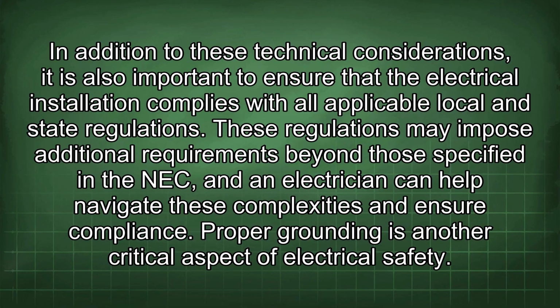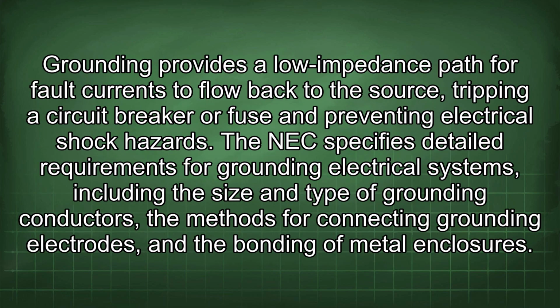Proper grounding is another critical aspect of electrical safety. Grounding provides a low impedance path for fault currents to flow back to the source, tripping a circuit breaker or fuse and preventing electrical shock hazards. The NEC specifies detailed requirements for grounding electrical systems, including the size and type of grounding conductors, the methods for connecting grounding electrodes, and the bonding of metal enclosures.